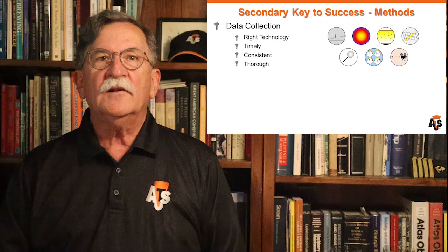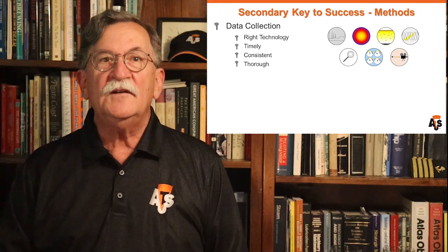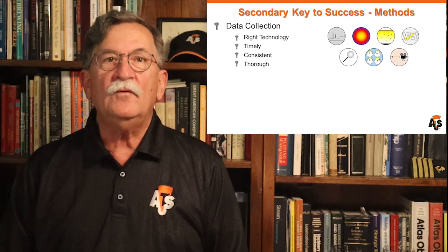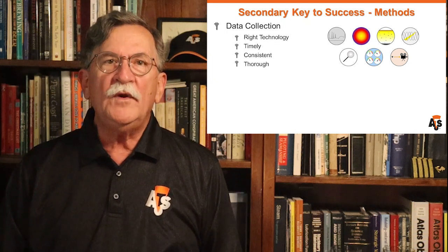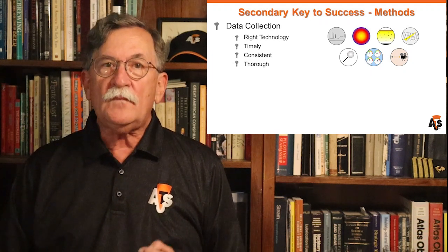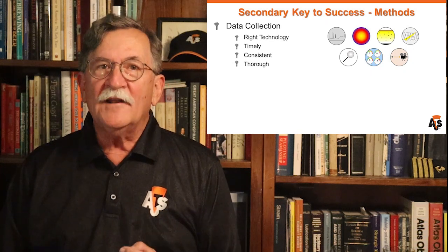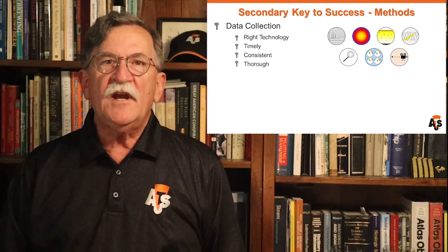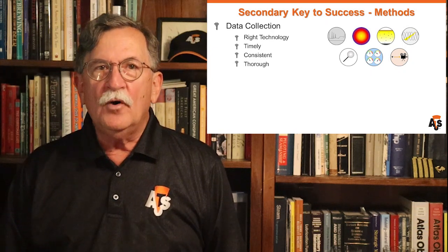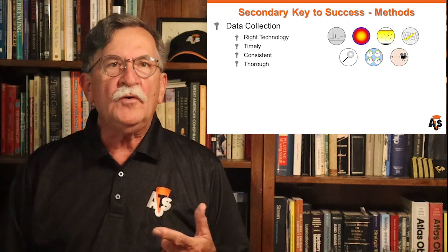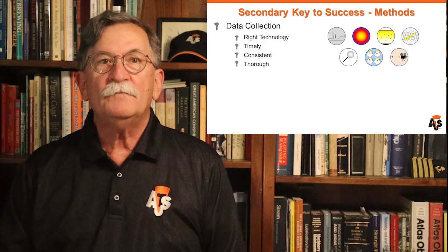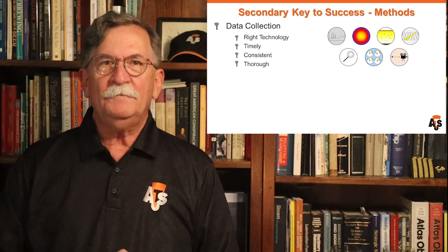Data needs to either be collected under consistent operating conditions, or we need the ability to record the machine operating state with the data so that we'll always know what was going on in the machine when the data was collected. We need to be able to compartmentalize the data so that we can differentiate between what is normal and what's not normal for each operating mode, speed, direction, load, or whatever that the machine goes through during its normal operating life. Think about your car for a minute.